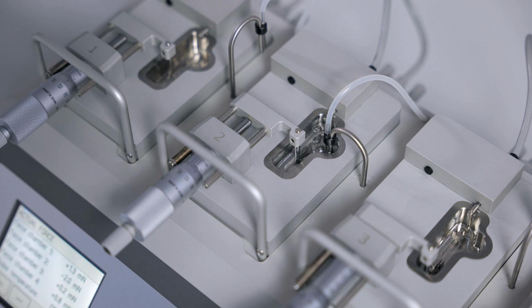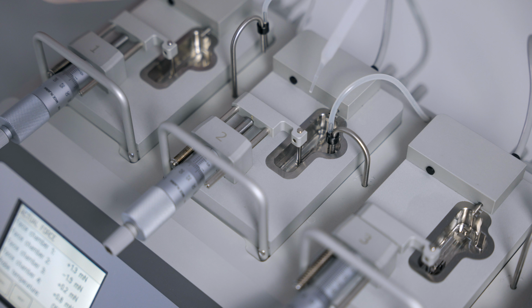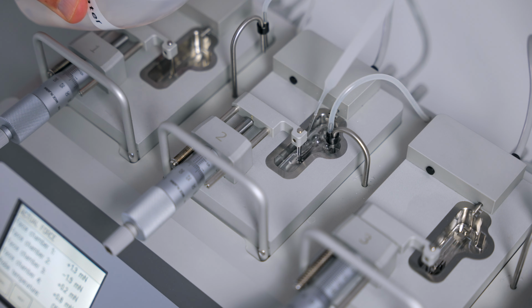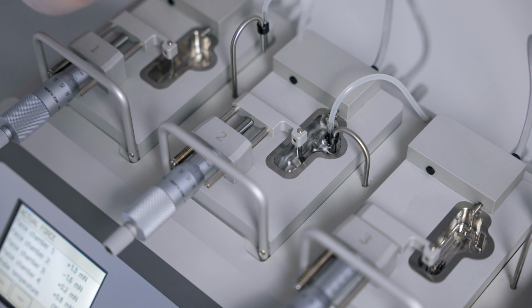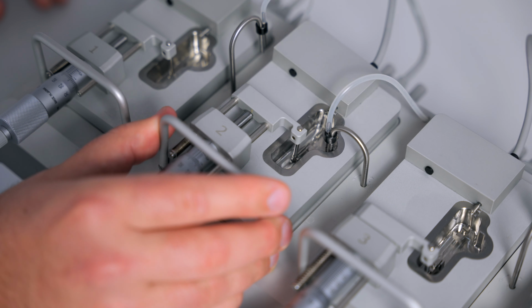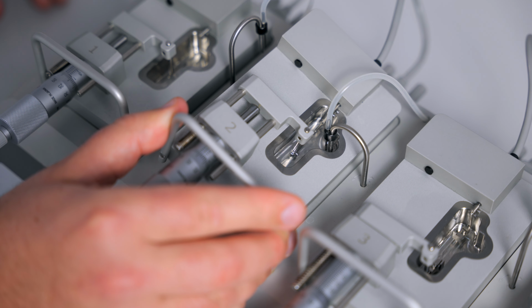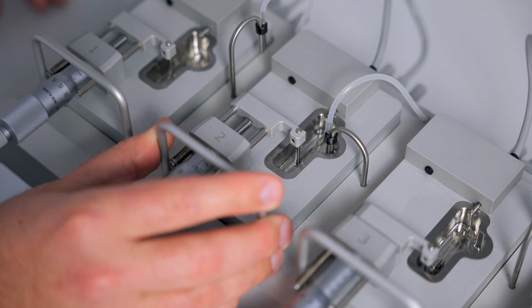In any of these circumstances, no matter what was used to clean the chambers, make sure you thoroughly wash several times with double distilled water. We don't recommend the heavy cleaning procedures too often as these can damage the organ bath chambers. If you notice red or brown discolorations on your chamber sides or the supports, we have a detailed cleaning protocol in the cleaning and maintenance section of this user guide.